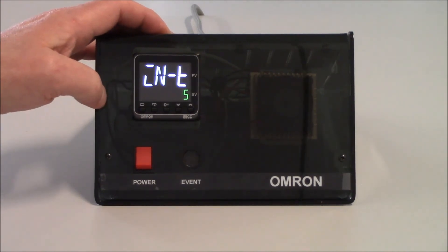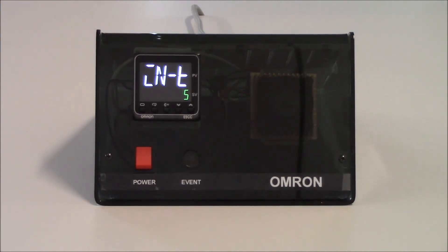Our outputs turn off and our very first parameter is IN-T — this is our input type. The first thing we need to do is determine the type of input we're going to provide to the unit, whether it be a thermocouple, RTD, or an analog input. By default the unit is set up for a value of five. With the instruction sheet, data sheet, or user manual, there will be a table showing the various input types available, and each different input will have a number based on that type.